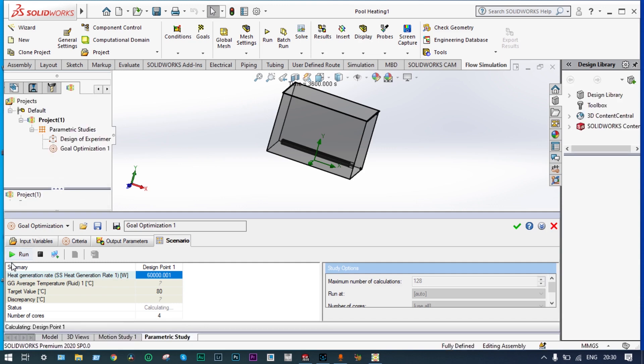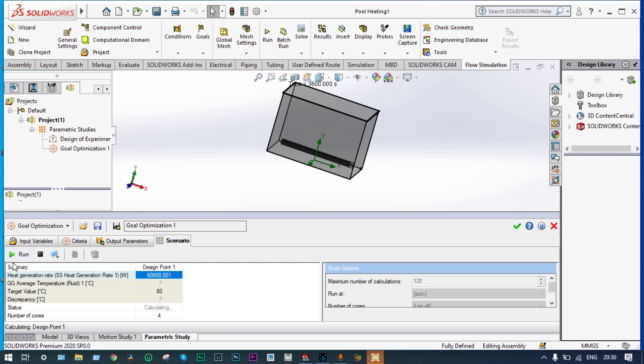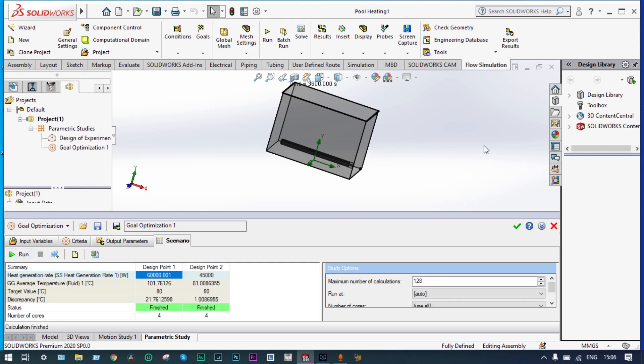Iterations have started. The optimizer first evaluates the maximum input value of 60 kilowatt, then the minimum value of 45 kilowatt, progressively narrowing the gap to find the optimum value corresponding to 80 degree centigrade. The optimization iterations are now complete — with the two boundary values it has converged, and we got an optimum result with a deviation of 1.0086 degree centigrade. We could minimize this deviation by narrowing the range further, but that would require another optimization run.